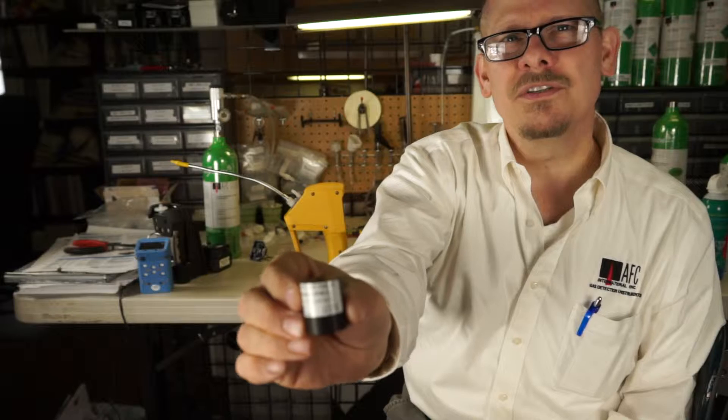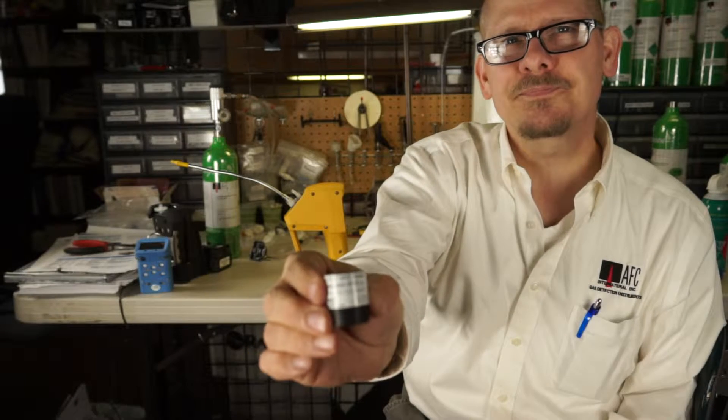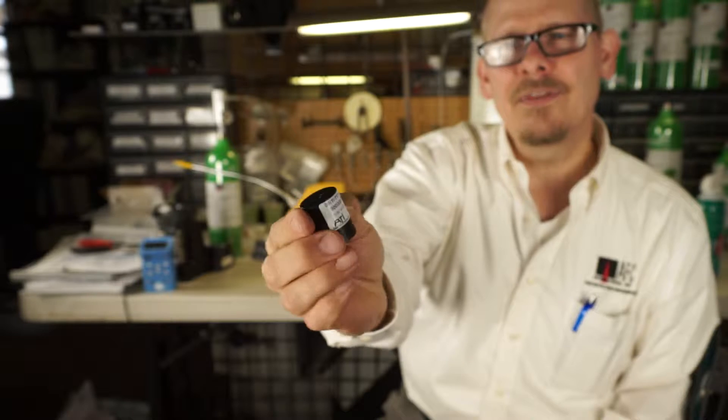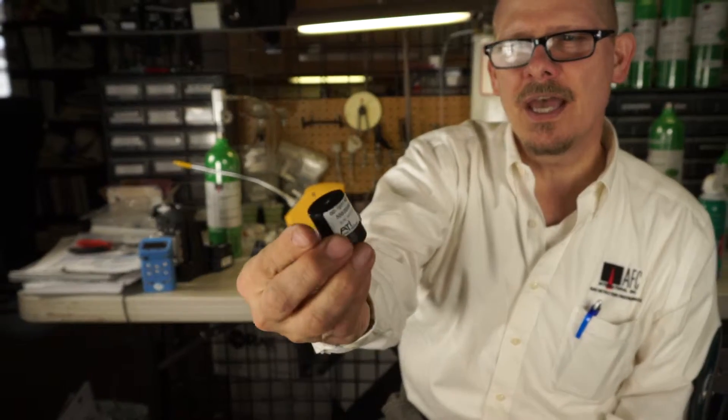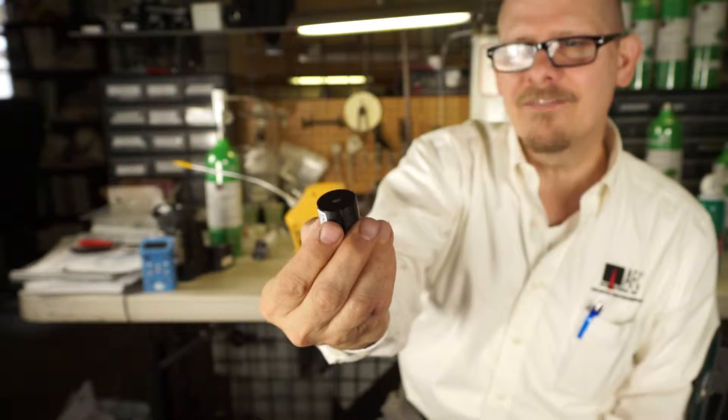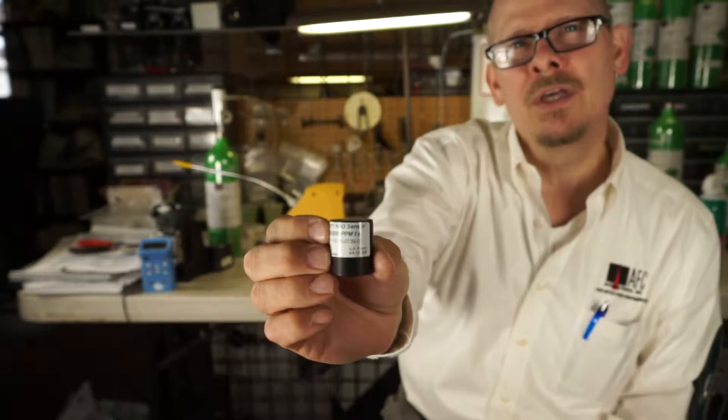This sensor in here is the ammonia sensor. I'm going to pull that out and bring it in so you can see it says ammonia on it. The ammonia sensor on the label says the serial number, the part number 00-1011 ammonia sensor, and then it also has 500/2000 ppm full scale.